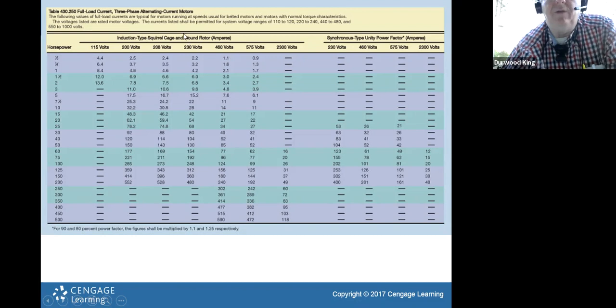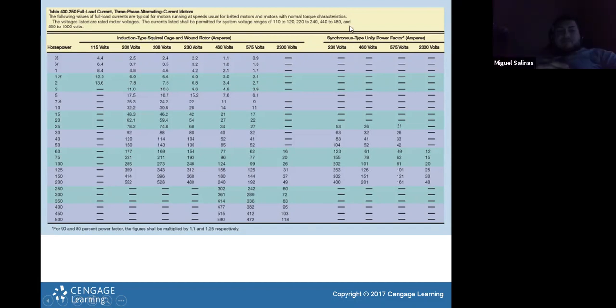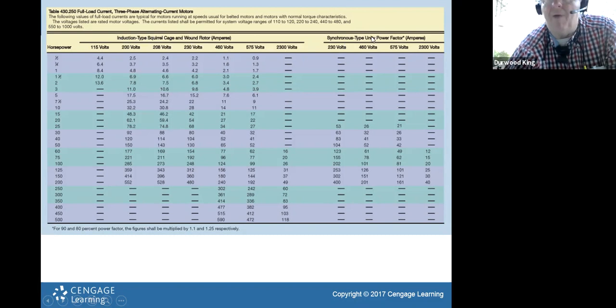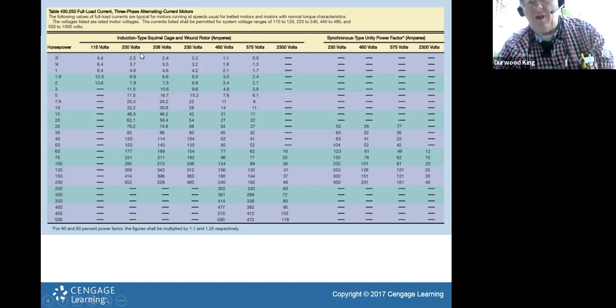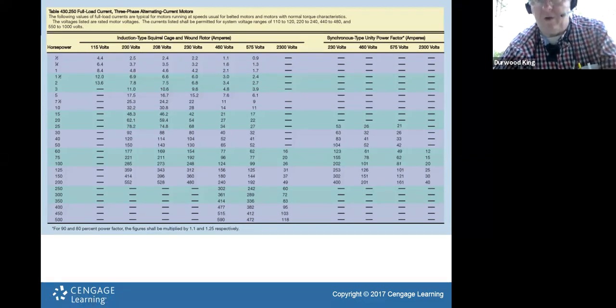Okay, so these motors here, this chart is going to be for induction type motors, squirrel cage and wound rotor. If you have a synchronous type motor, that's a more sophisticated type motor, more precise on speed, then it's a whole different chart over here. So it depends on the windings in there, what kind of motor, and that will be printed on your nameplate.